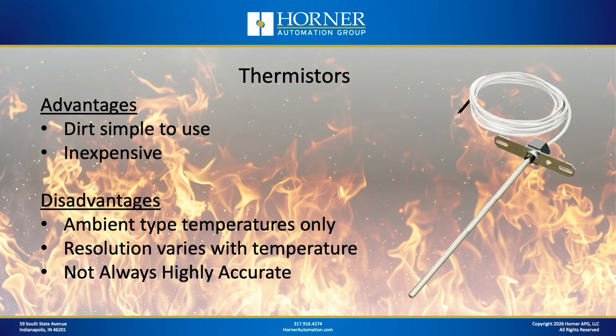All right, now let's dive into the final type of temperature sensor we're covering today, and that is a thermistor. So the advantages of a thermistor are they are dirt simple to use. They couldn't get any simpler, and they're extremely inexpensive, okay? They're very, very cheap. But they have some disadvantages, which is why they aren't extremely widely used in a lot of different applications. They really only deal with a very limited temperature range, typically within the ambient range.